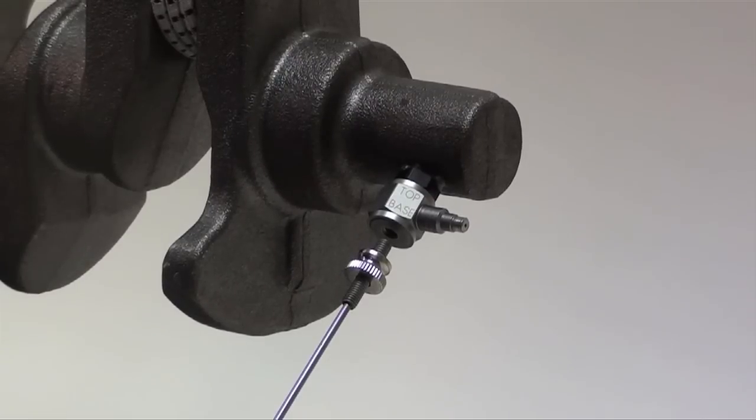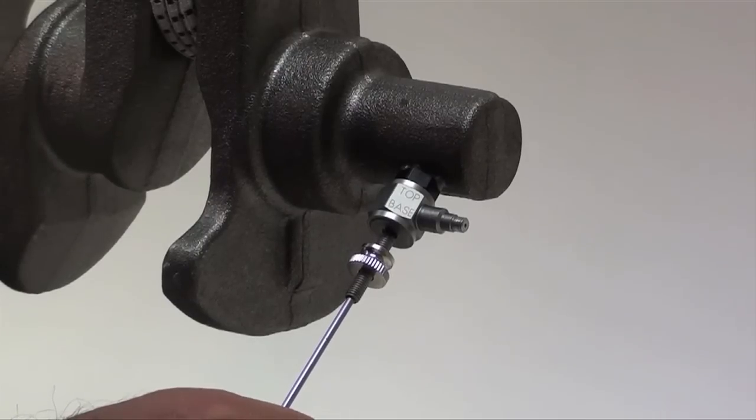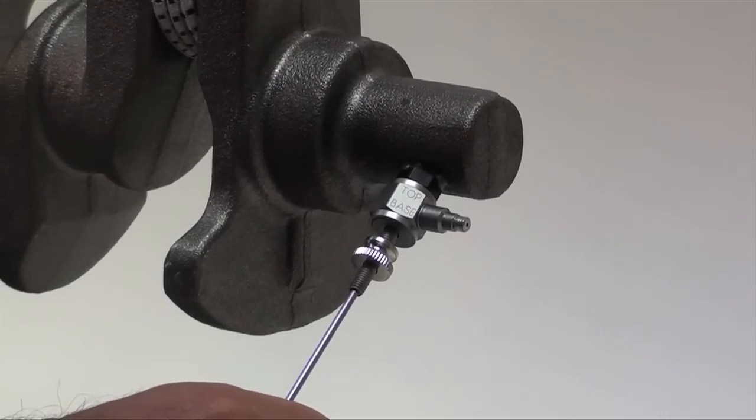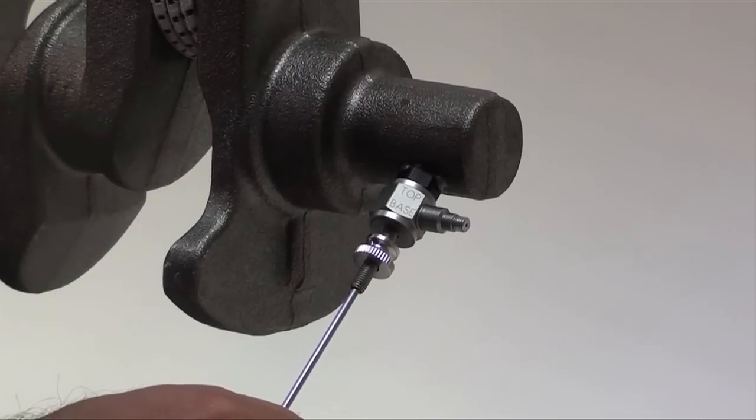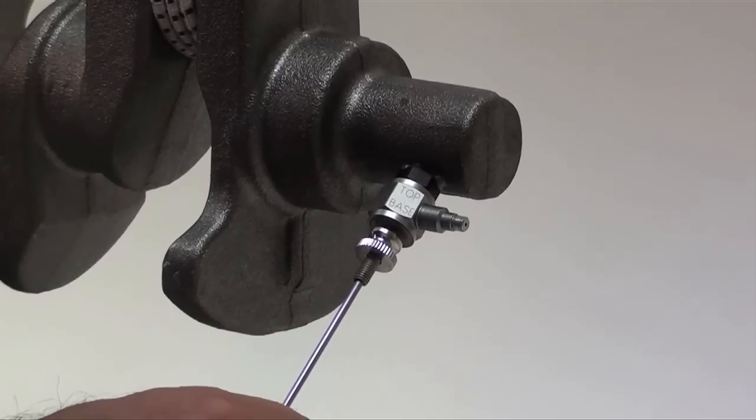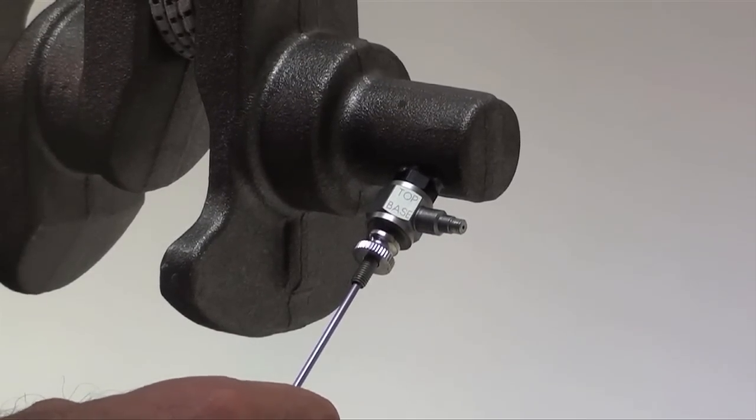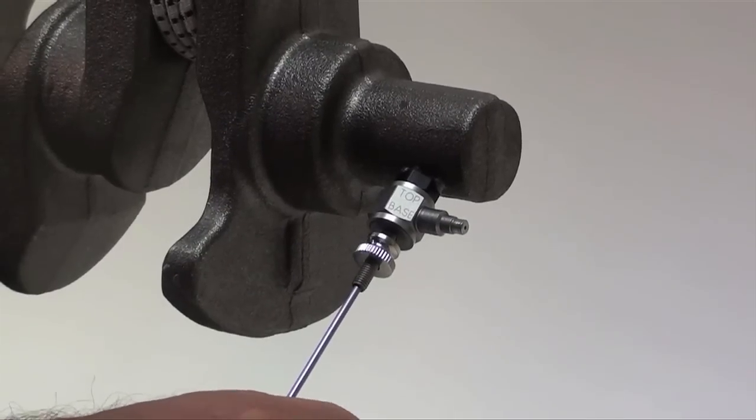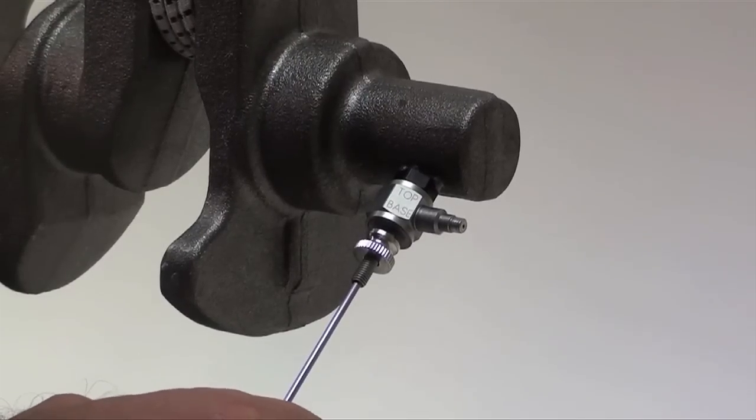Once you're satisfied with the alignment of the stinger to the load cell, a last alignment check is actually threading the stinger into the base of the load cell. And if alignment is adequate, the stinger should thread into the load cell very easily. If it does not, that means there's some side load or something that's not quite right. But in this case, the stinger threads very easily into the load cell, which means we have good alignment.